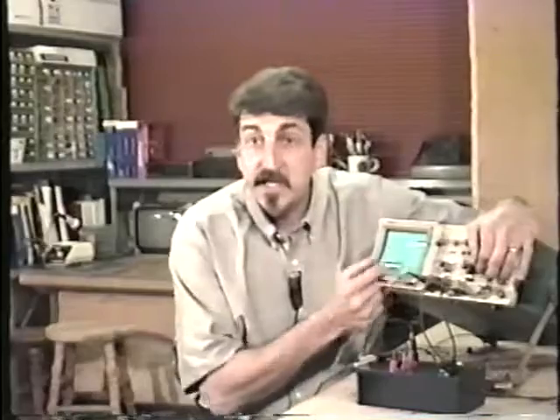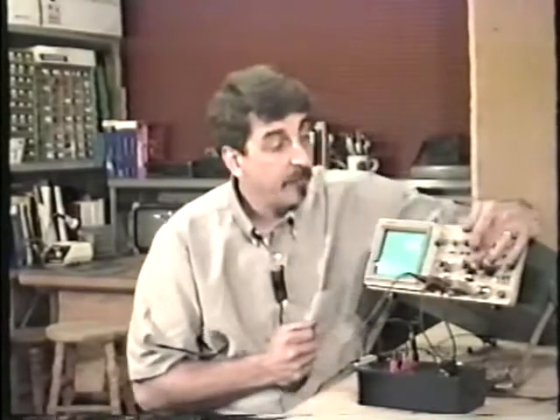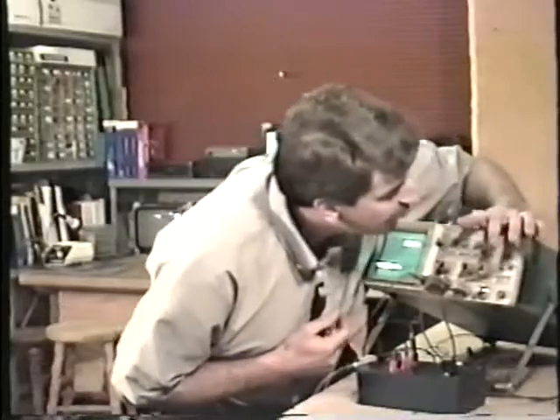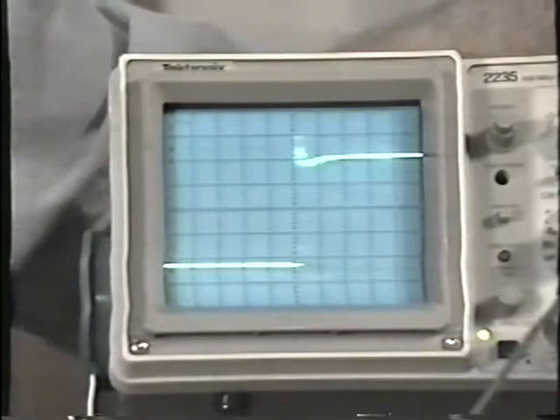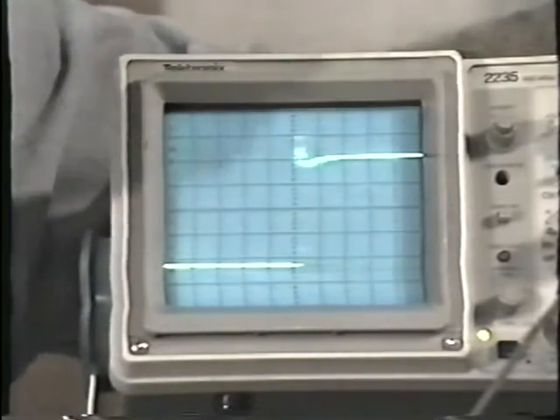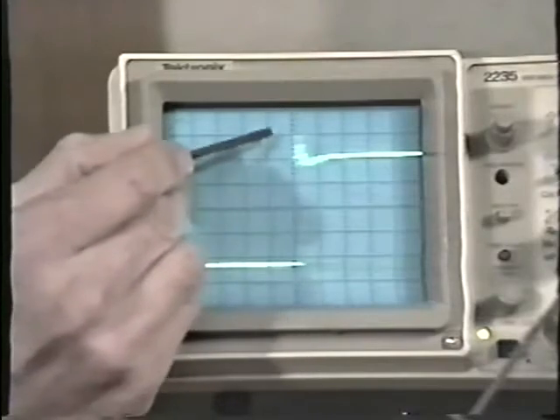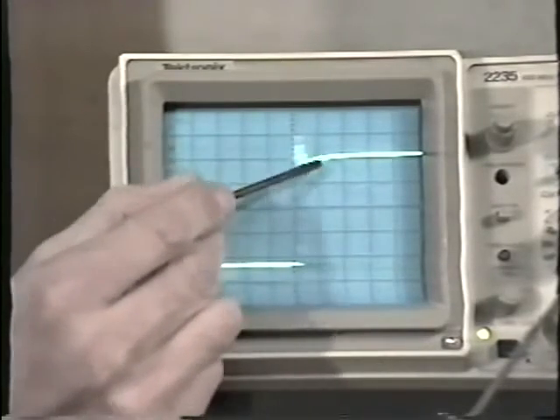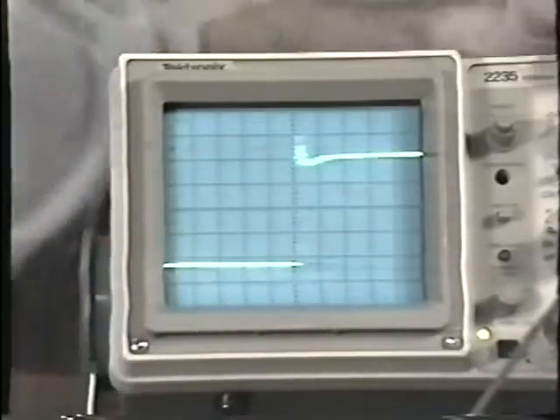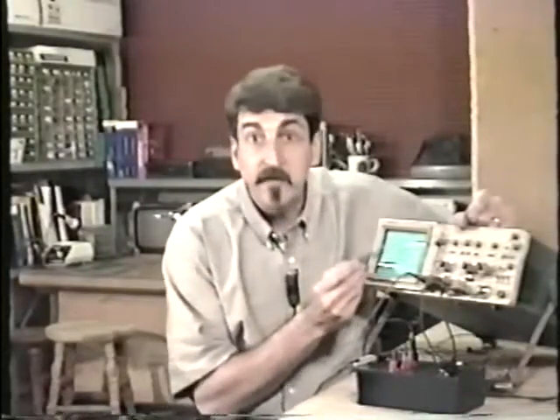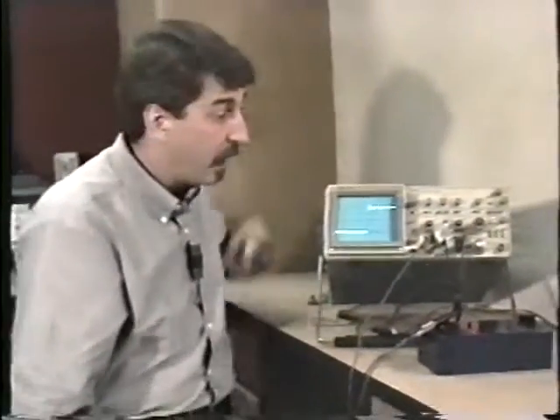The sweep has expanded to 10 times its original size. For example, right now the sweep is set on 5 microseconds per division. When I pull out the times 10, we're now at 0.5 microseconds per division, and we can get a better look at this little glitch here. Now, it's somewhat unstable, and that's perfectly normal. When you start getting into very, very fast time settings, you can expect some instability in the waveform. And don't forget, when you're done using the times 10 magnifier, reset it back to its normal position.